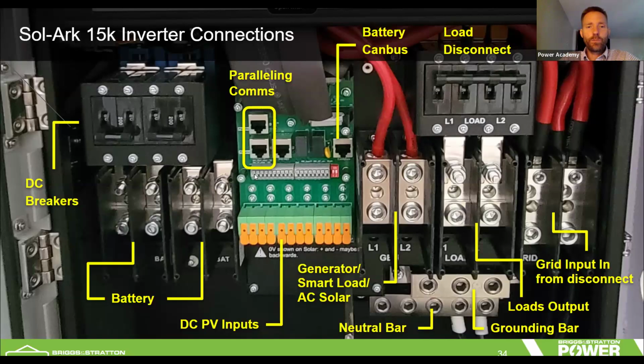Here is the comms bar on the Sol-Ark 15K, and I'll break that out in a separate slide. These are your solar inputs. You have 3 independent MPPTs, 6 overall inputs. So keep in mind that when you're combining 1 and 2 with 3 and 4, you're paralleling these units. It's not important to have the same amount of current on each of those when you're paralleling them, but it is important to have the same number of panels, or at least an approximate same input voltage on your MPPTs. That'll allow the MPPT to function well when you're combining strings of solar. So you've got 3 independent MPPTs, 6 overall solar inputs.